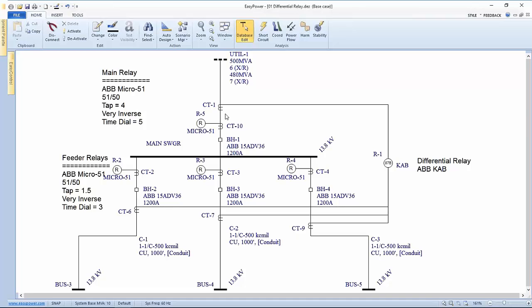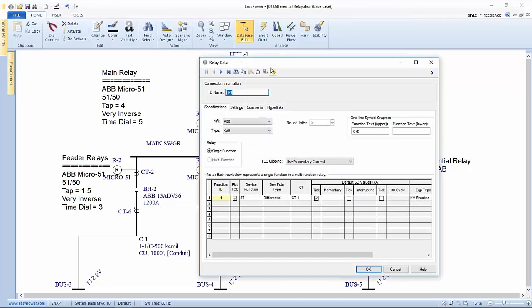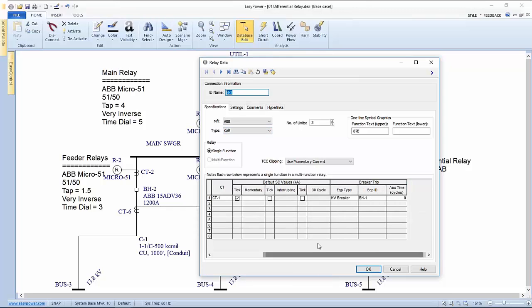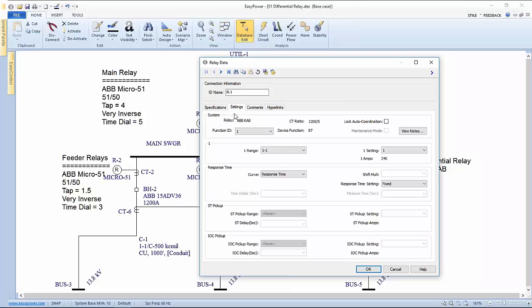What's nice about this is that although we only show this connected across the switch gear itself, this could incorporate several layers of voltage distribution, including transformers and other sub switch gears, as long as we're summing the total current going out of the whole system and comparing it to whatever the current coming in is. In effect, we're comparing the input and the output and nulling it out. And if there's a differential between them, that's when we want this relay to activate. When we go to set this up, if we look at the way easy power requires this, we effectively set it up on a similar basis where we've got the manufacturer's ID, the function and the relay that it's going to be connected to.